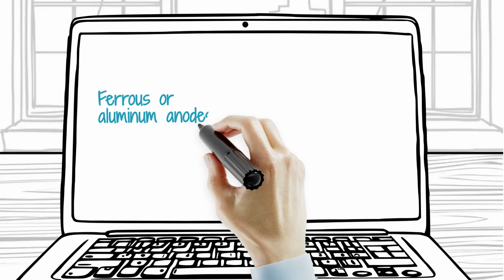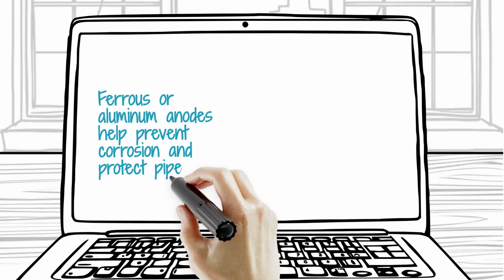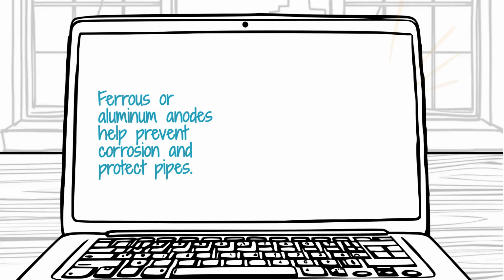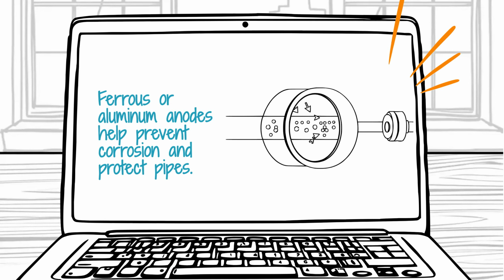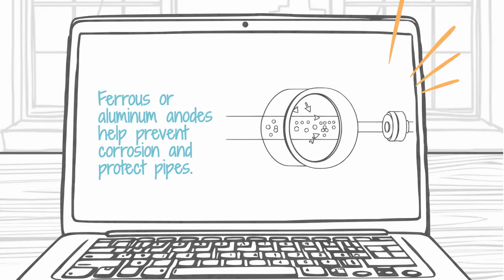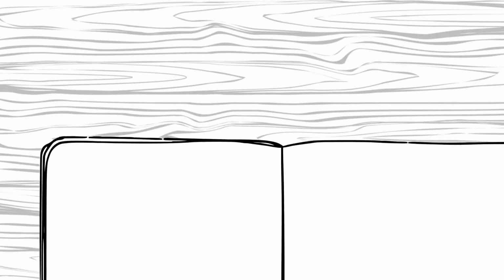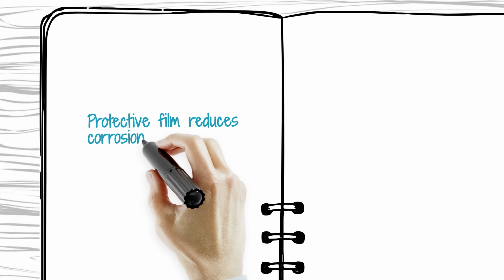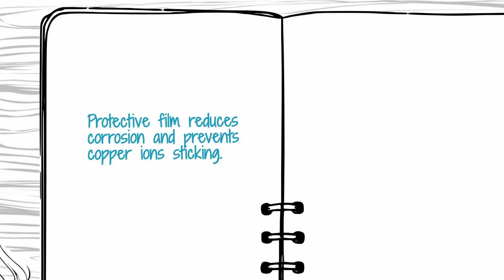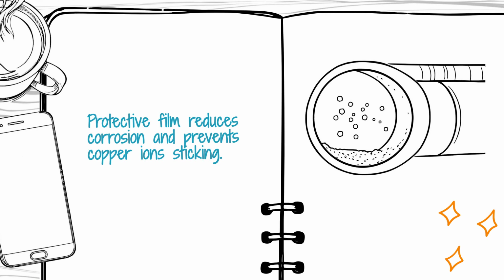The second is a ferrous or aluminum anode. When current is passed through this anode, it releases ferrous or aluminum ions. These ions are not primarily for anti-fouling, but rather for forming a protective gamma ferric oxide film on the internal surfaces of the cooling pipes and heat exchangers. This film helps prevent the copper ions from adhering to the metal surfaces and also acts to reduce corrosion, providing dual protection. The entire system is controlled by a dedicated control panel.